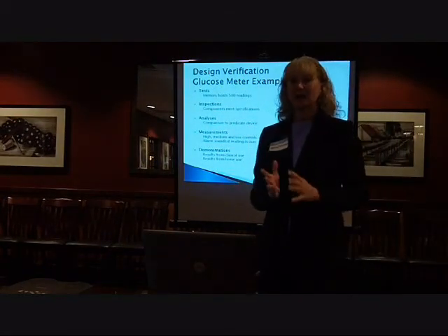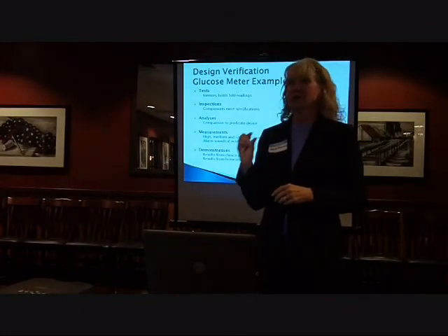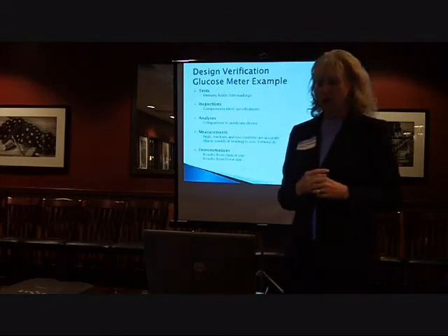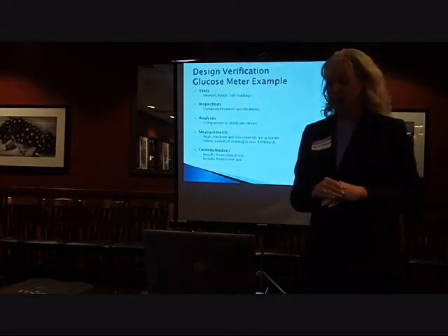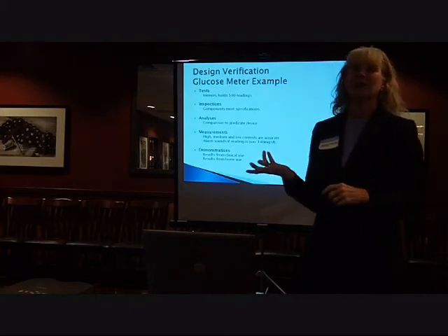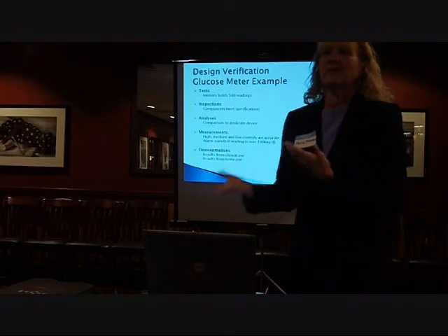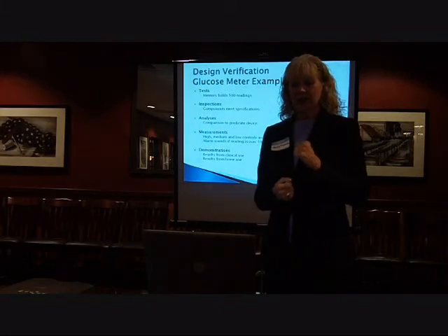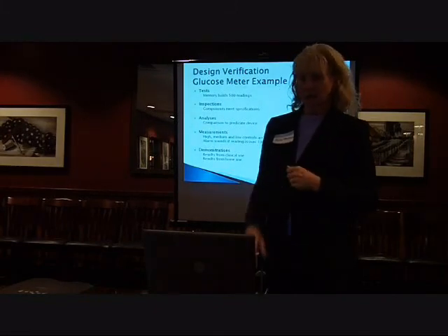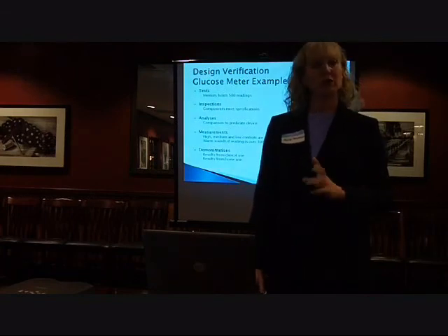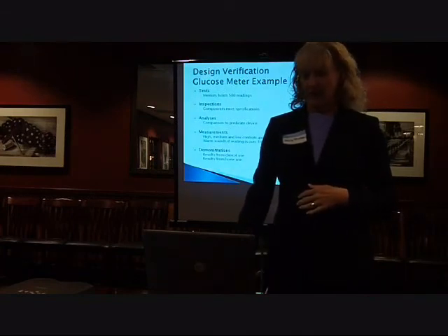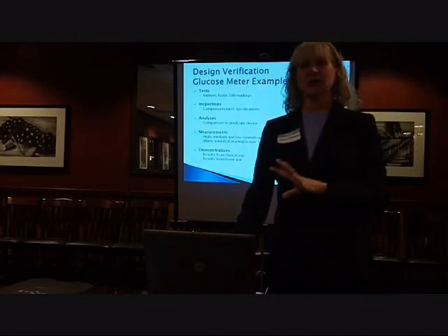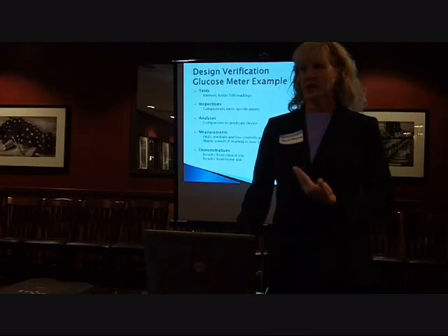Measurements: in this case, you may have high, medium, low controls. I usually send out a little control sample with the meter so that you can do that check, make sure that it's on target. You might check to see that the alarm sounds if the reading is over 140 milligrams per deciliter, or whatever alarm you've decided to do. And then you look at the demonstrations. You're verifying this by looking at some clinical use, home use. You've done some studies where people have played with it, maybe not necessarily formal clinical trials or anything like that, but you had some interaction and some feedback at this stage.